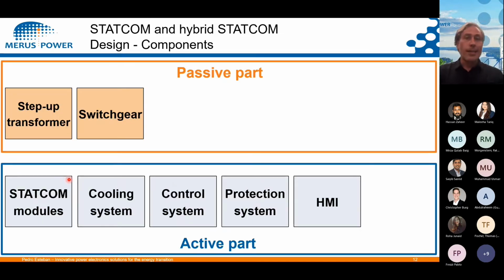Components. If we keep it very simple, a STATCOM will have these components: a step-up transformer if needed, certain switchgear, and an active part where we have the modules. Cooling is very important for these devices, usually liquid cooling, and then the control and protection system with the HMI.